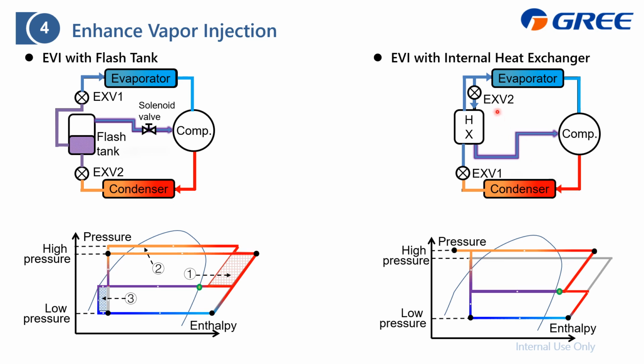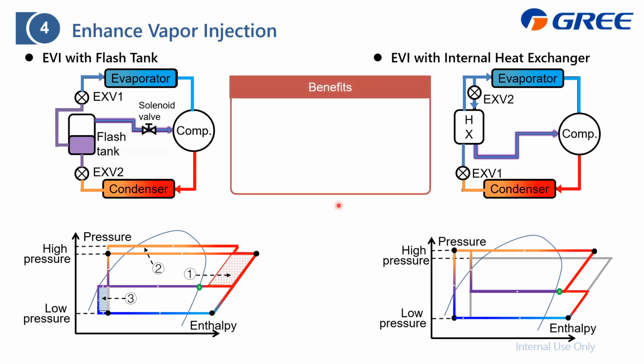And then we can use this EXV to control how much amount we need to inject into this compressor according to system demand. So it becomes this one, and also we can extend the evaporator range by raising the subcooling. So from the result, the benefits are also the same. 1, 2, 3.